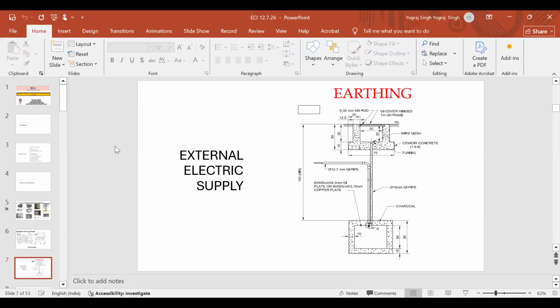How is that media created? Layers of coal, salt, and earth. So that makes it. Other than that, there are some chemical earthing materials and other things which retain moisture in the media. So the better the moisture content in the media, the better the fault dissipation.